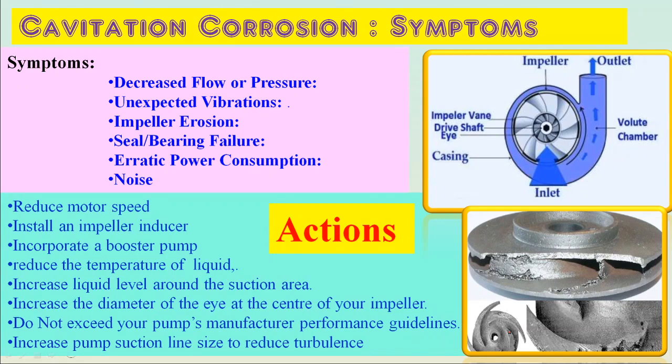Now what are the symptoms? How do you realize that there is cavitation in your system? First, a decrease in flow or pressure, because there will be a restriction and turbulence. You will see unexpected vibration in your pump, casing and piping.